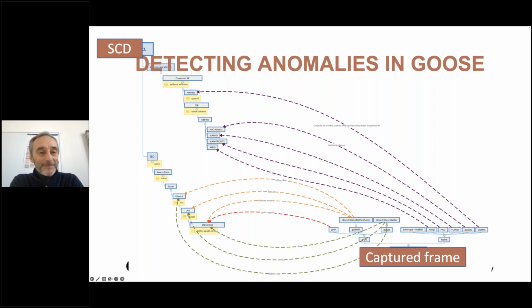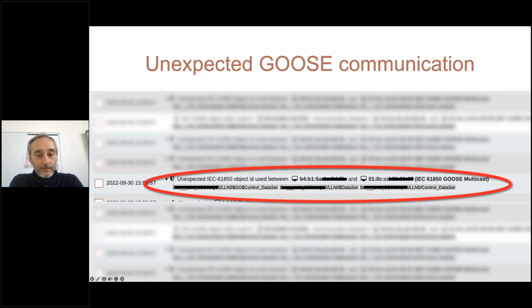What you get looks like a CIA report, heavily redacted, because I'm protecting customer data here. But you will see, for example, that this communication, this data set, this control block between this MAC address and this multicast destination is unexpected, since it wasn't defined. Then you can investigate whether this is a rogue device or an IED misconfiguration.